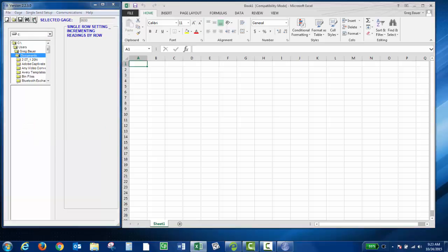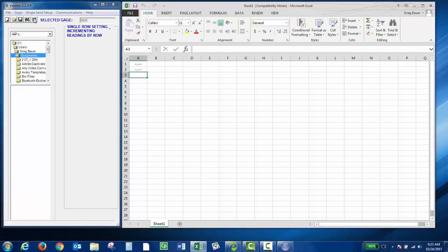You should now be able to click the single send key or the send key on the instrument. If there's no live thickness reading on the screen of the instrument, it's just going to send those dashes. If you have a live thickness reading and you press the send key, it'll single send the data to the spreadsheet, as you can see.